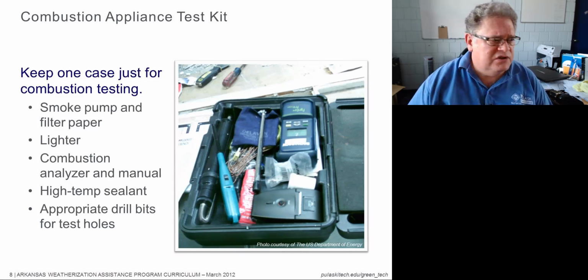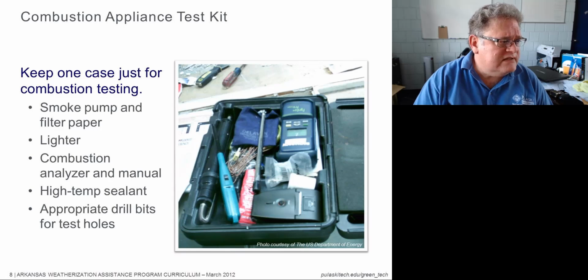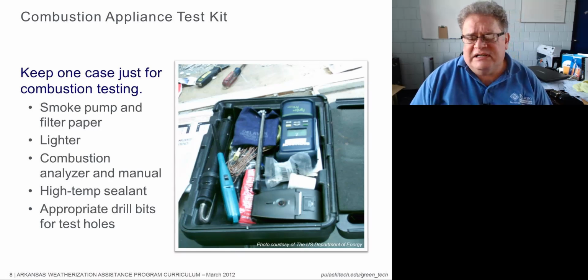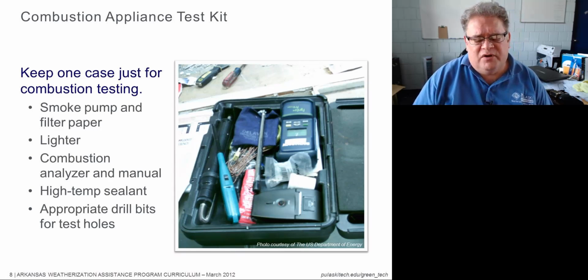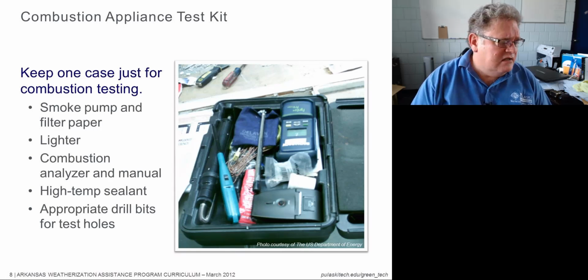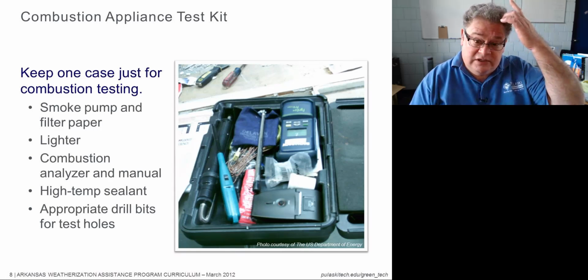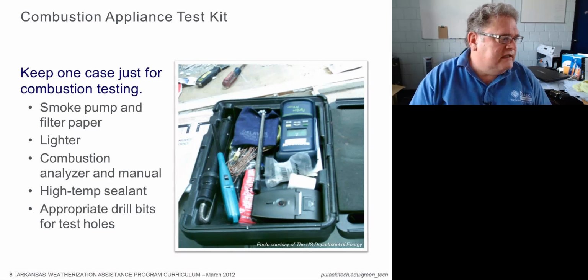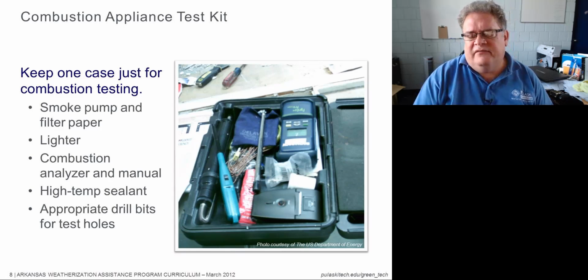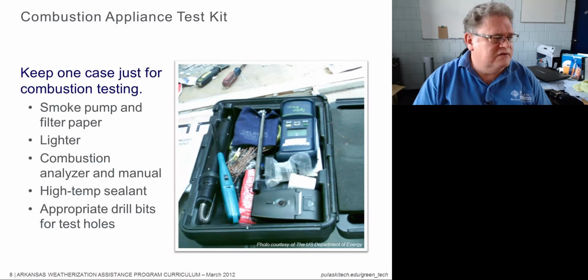That's what's in this red tube right here. This is high temperature RTV silicone, and it's an automotive style product. It's fine as long as it meets the ASTM number set out in Appendix A for air sealing. And then appropriate drill bits for the test holes that you're going to drill.